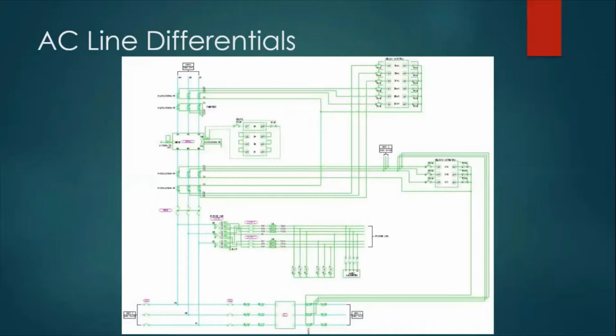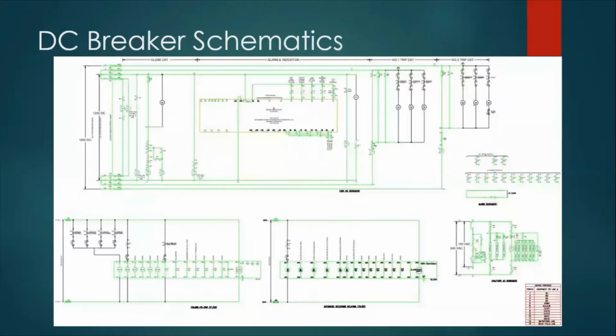AC line differential schematics will show the protection scheme surrounding the breakers and the transformer, while providing a wiring level view of each relay. Major inputs and outputs are wired to show mutual interactions. DC breaker schematics show the individual protection devices associated with each breaker and the transformer. These show what can trip and reclose. If operation or failure occurs, alarms and lights were wired to alert system operators through the annunciator.